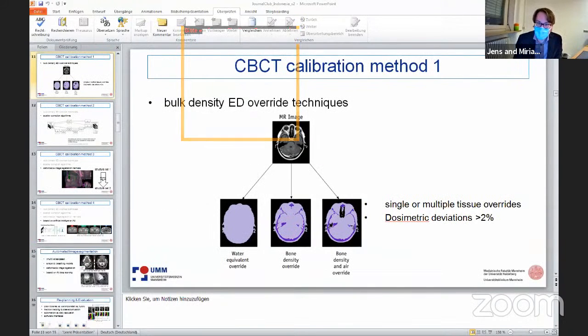Calibration methods. Now we'll go there one by one. The first calibration method I want to mention, so how to calibrate, be it either an MR image or a cone beam CT, to reflect the actual electron density information, is you just identify certain regions and you perform what we typically call a bulk density override. So you assign either 1, 2, or 3 fixed electron densities to certain regions of interest. In this particular nasopharynx example, it would be water for the brain, so electron density 1. Then you have the skull identified, which would have 1 fixed electron density, and you would have here then the nasopharynx region, which you would basically assign air to.